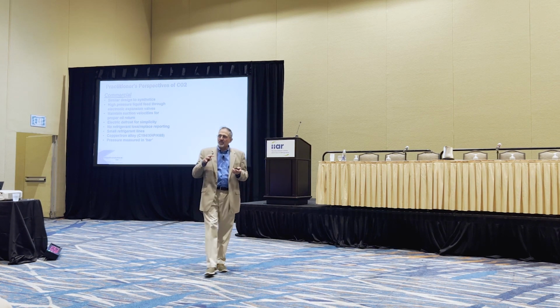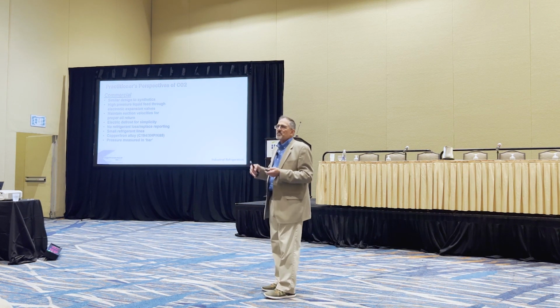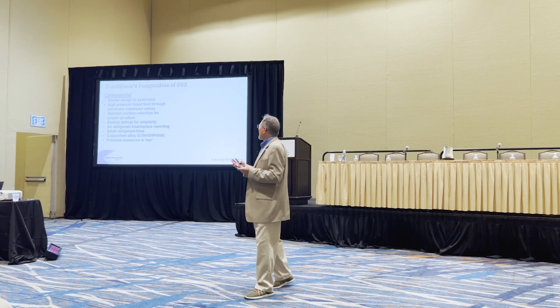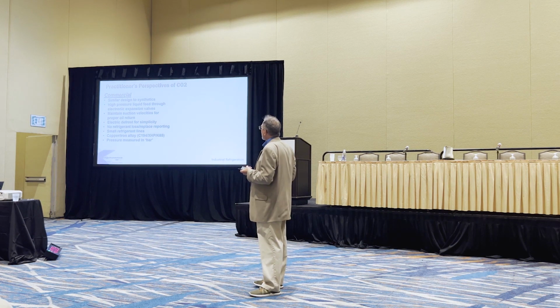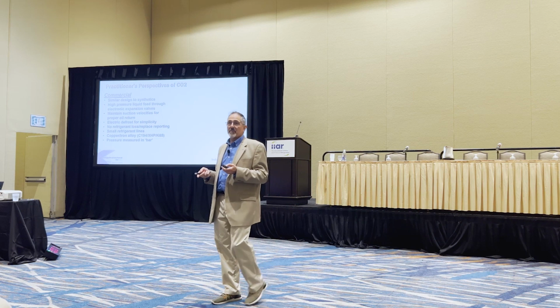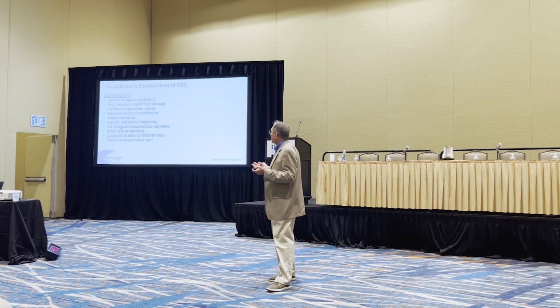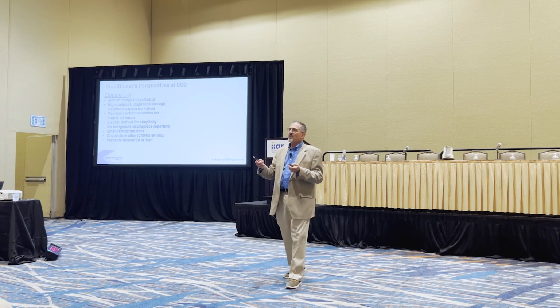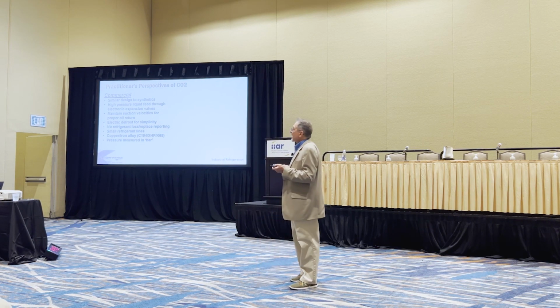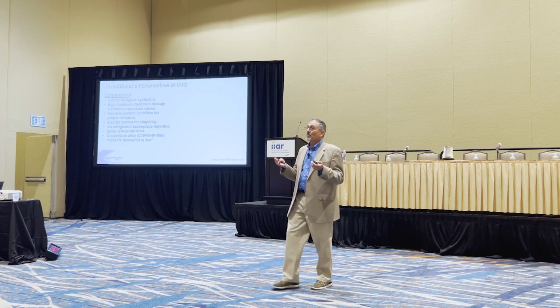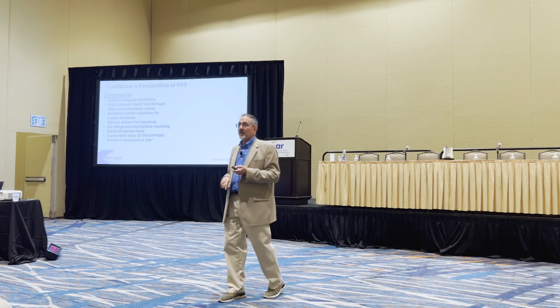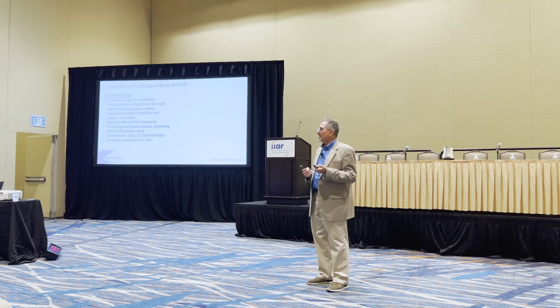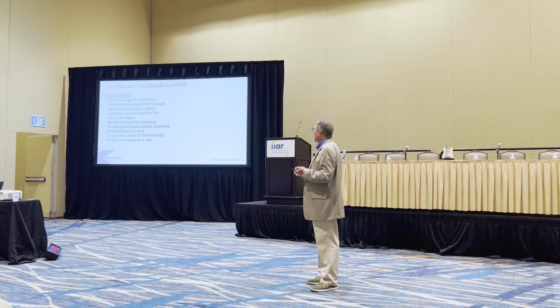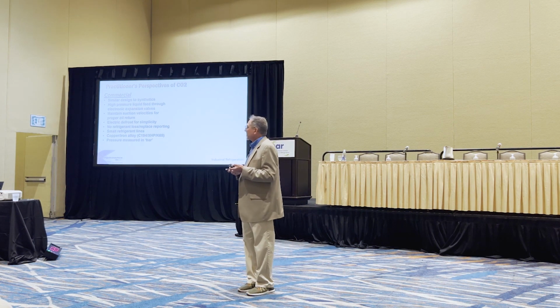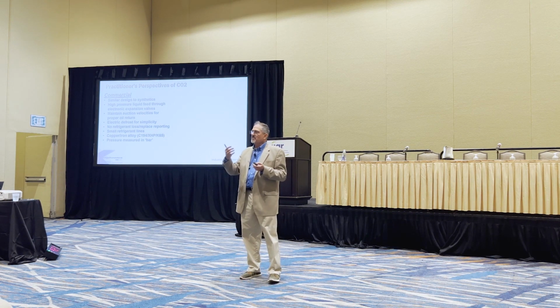As I look back on the introduction of CO2 refrigeration into the industrial space over the last 5.5 years that I've been with Hillphoenix, there's different perspectives depending on who you're talking to. And so from the practitioner standpoint of commercial refrigeration, who have done mostly synthetic refrigerations, what they see is the design of a CO2 system is very similar to that of the synthetics. High pressure liquid is fed to expansion valves that then meter that liquid into the evaporator to vaporize, absorb heat. In the case of CO2, it's always an electronic expansion valve. There's some real beauties associated with an electronic expansion valve. It has a wide range of operation and actually very forgiving to even perhaps flash gas that might be introduced to the entrance of the electronic expansion valve. It's necessary to maintain suction velocities for proper oil return. So oil is miscible with synthetics, it's miscible with CO2.